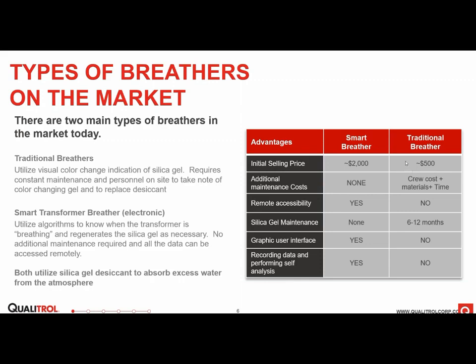Some of the advantages of a traditional breather is that they're very cheap up front. It's a very low-cost investment to install one of those on a transformer. But some of the disadvantages is that you need to send a crew out on a time schedule or based on visual indication. So either you need to have a visual inspection schedule, which would turn into a replacement schedule. And then they offer, obviously, no data recording, no trending, things like that.